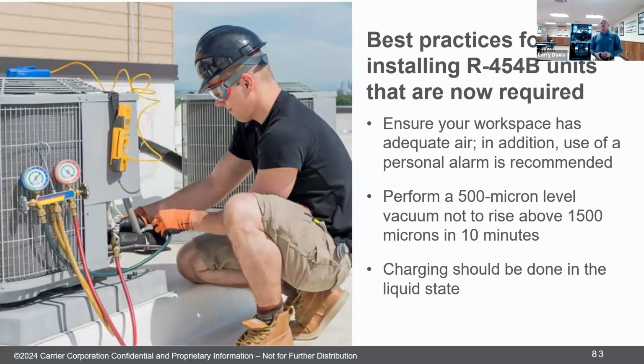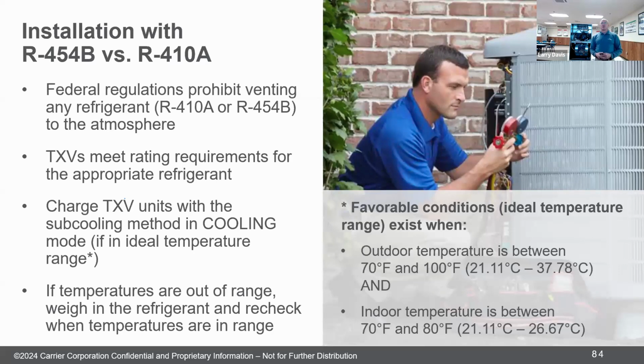Your vacuum, you're going to get down to a 500 micron level vacuum. Make sure it holds for 10 minutes, and then you charge with the liquid. Okay, that's on a new installation. So comparing the two, on charging them, you can't vent either refrigerant. That's been a standing rule that hasn't changed, even though now we have a refrigerant that has a low global warming potential and no ozone depletion. We still can't vent it. We still have to recover it.